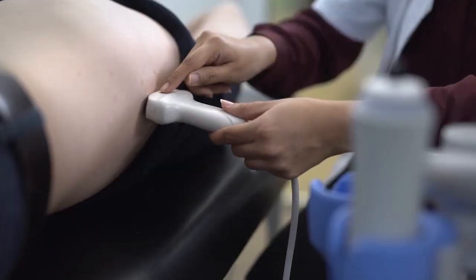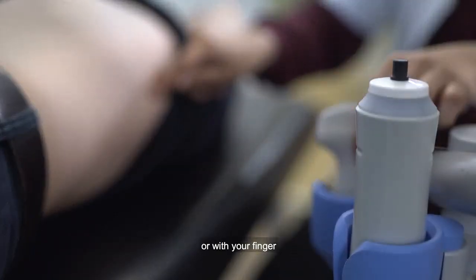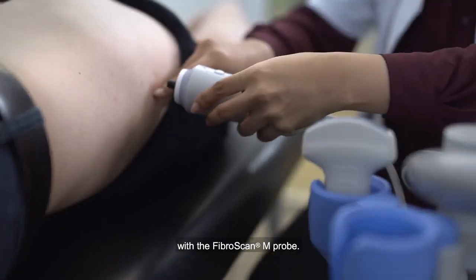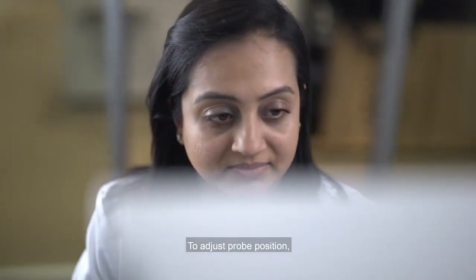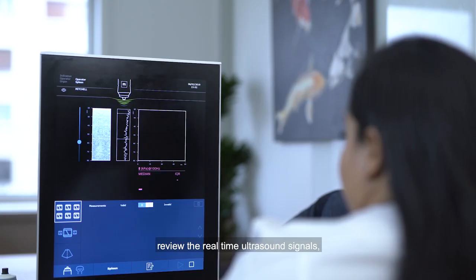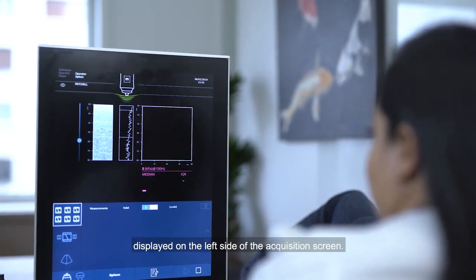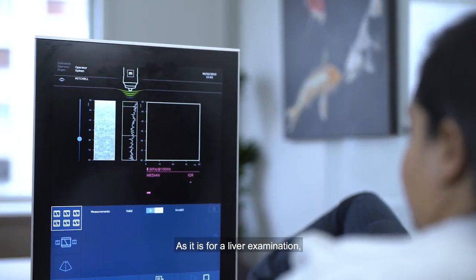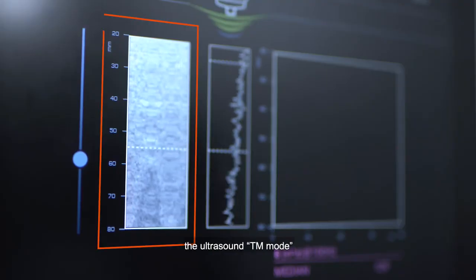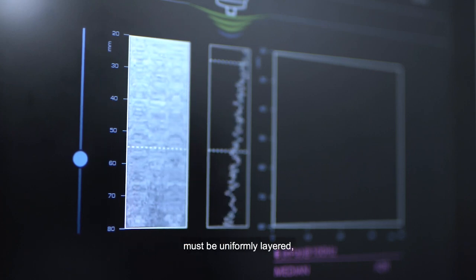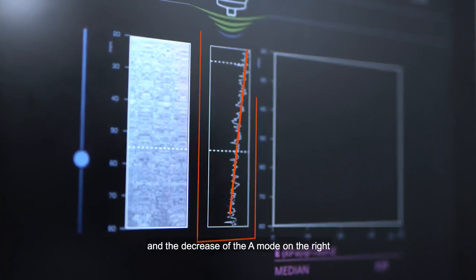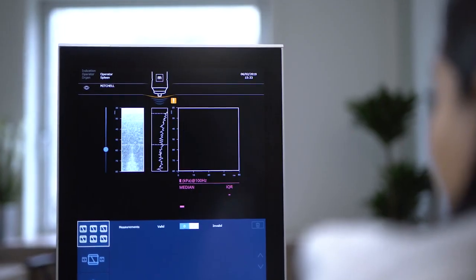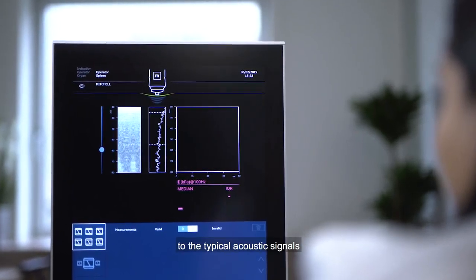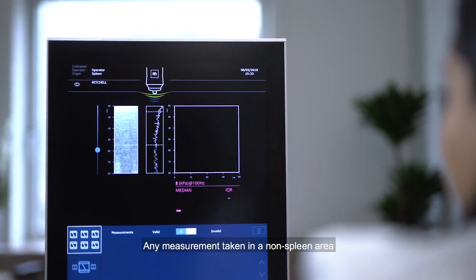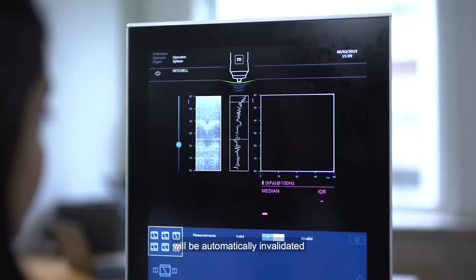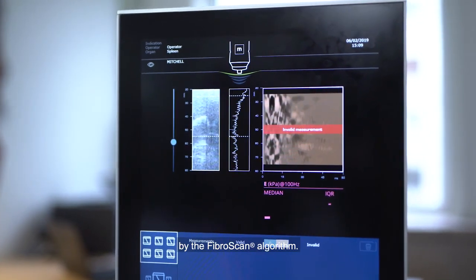Once the spleen is found, mark that point with a pen or with your finger and swap the probe with the FibroScan M probe. To adjust probe position, review the real-time ultrasound signals, also known as TM mode, displayed on the left side of the acquisition screen. As for a liver examination, the ultrasound TM mode on the left must be uniformly layered, and the decrease of the A mode on the right must remain linear, which together correspond to the typical acoustic signals for the spleen. Any measurement taken in a non-spleen area will be automatically invalidated by the FibroScan algorithm.